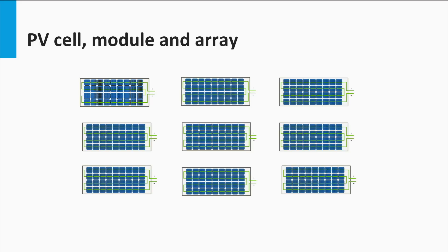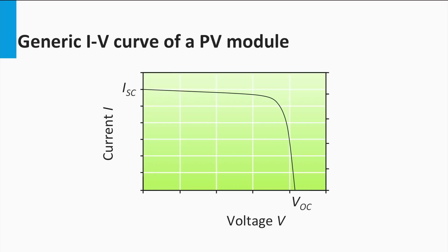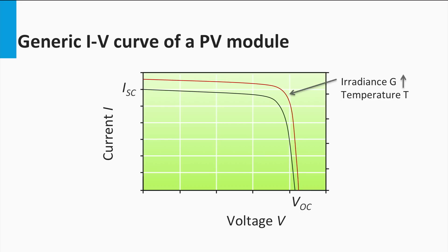Let's look at the simple IV curve of a solar module. The IV curve is nothing but the current-voltage curve. This IV curve of a PV module is defined for a unique set of temperature and irradiance conditions. For instance, if the irradiance or illumination were to increase, the IV curve would also change to a higher level. In general, a higher irradiance gives a better IV curve, but a higher temperature gives a worse IV curve, and vice versa.